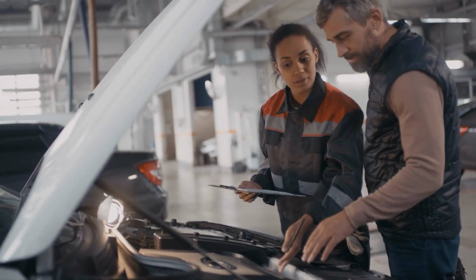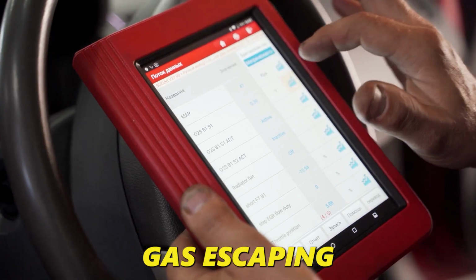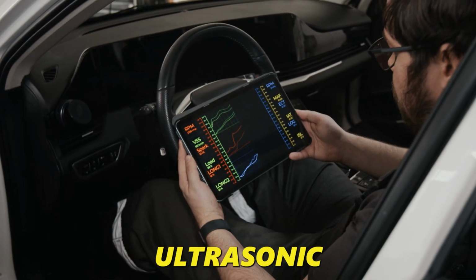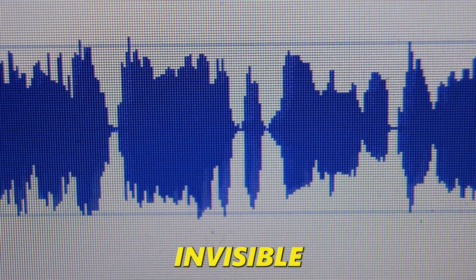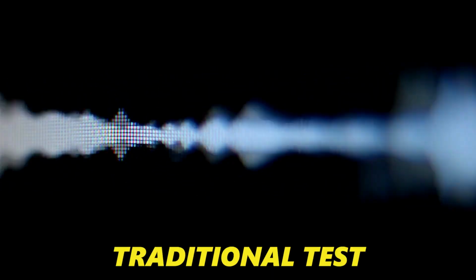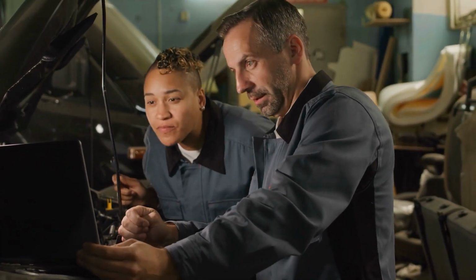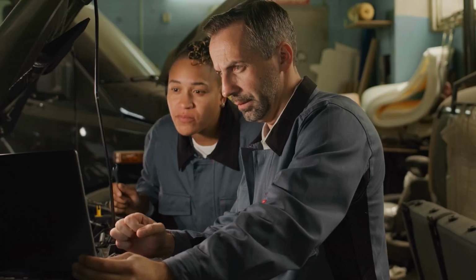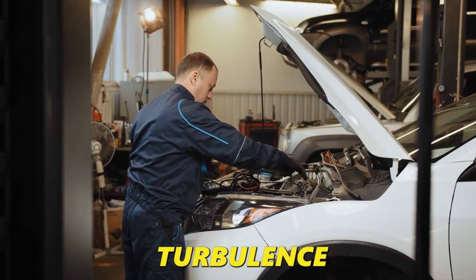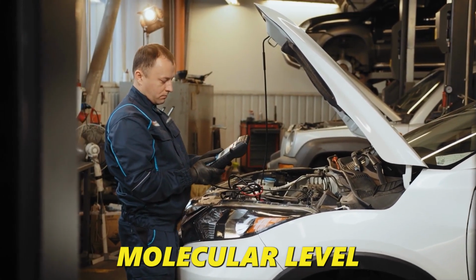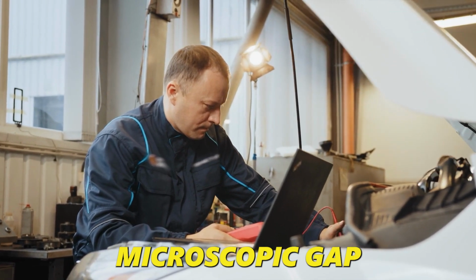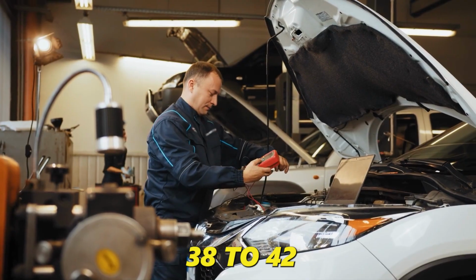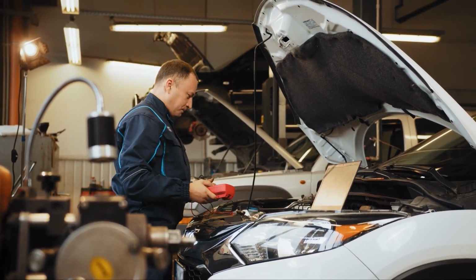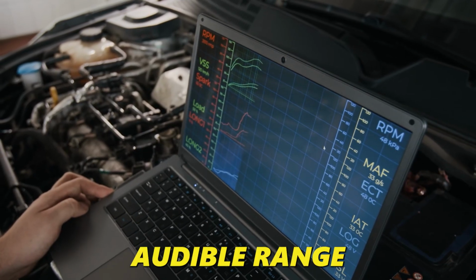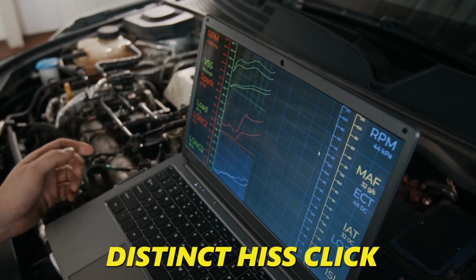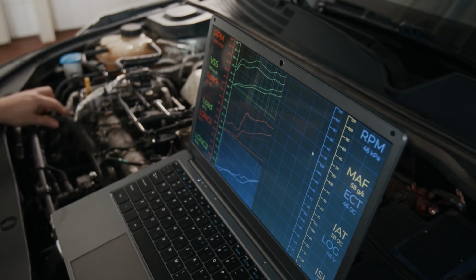The leak we're looking for has a signature, not a visual one. An acoustic one. Pressurized gas escaping through a microscopic orifice creates an ultrasonic frequency high above the range of human hearing, completely invisible to every traditional test, but not invisible to this. Ultrasonic leak detection has been used in industrial refrigeration and HVAC for decades. It works on a simple principle. Escaping gas creates turbulence. Turbulence creates sound. At the molecular level, the friction of high-pressure refrigerant forcing through a microscopic gap generates ultrasonic waves in the 38 to 42 kilohertz range, depending on the system pressure and the size of the breach. This device translates those frequencies down into the audible range. What was silent becomes a distinct hiss, click, or crackling sound that changes in intensity as you move the wand closer to the source.